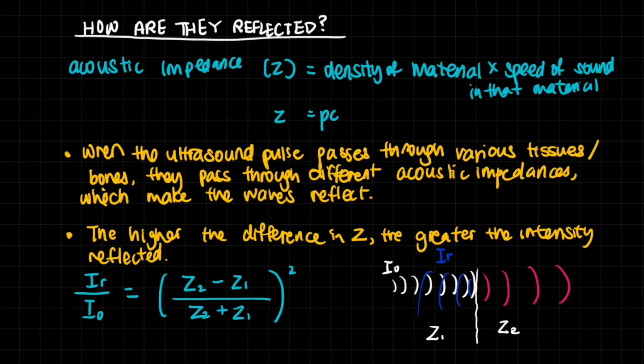One very key element is that ultrasound is reflected at different boundaries. How and why are they reflected? I've previously mentioned that boundaries between materials that have different acoustic impedances will reflect the sound wave. Here is what acoustic impedance is: it's denoted by Z, and it's basically the product of the density of the material and the speed of sound in that material - Z equals ρc.